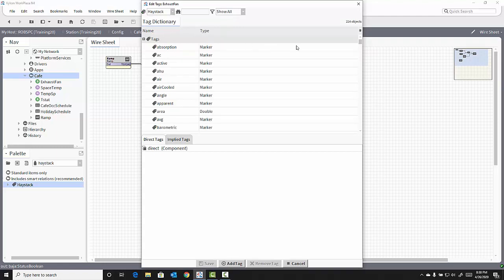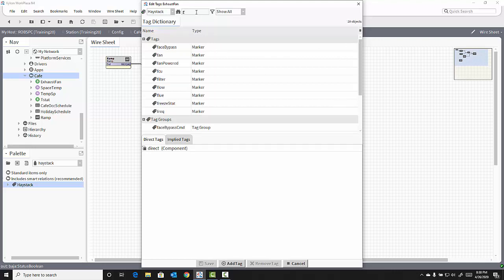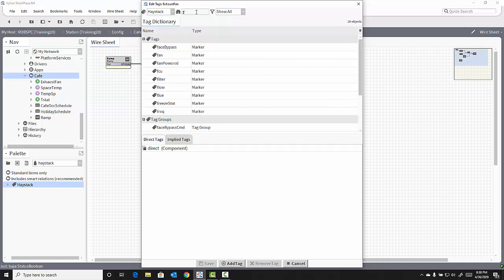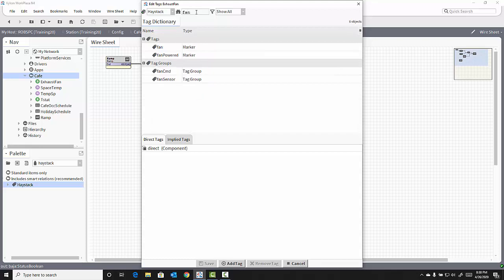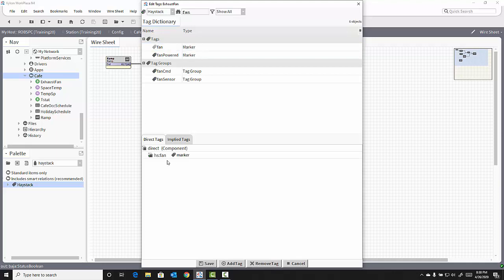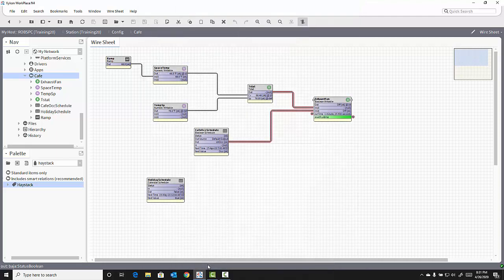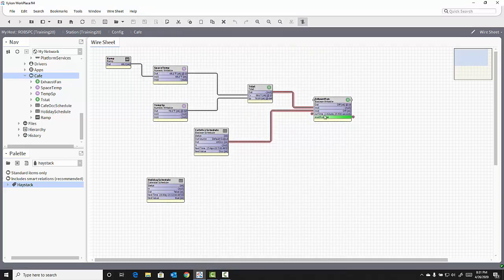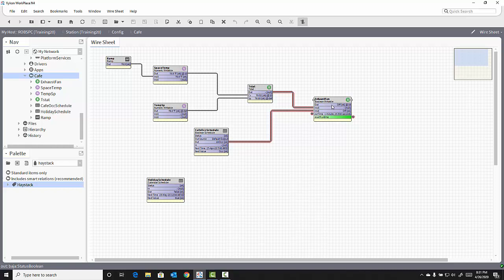Now, I could scroll through all the different tags that are available from that dictionary, or I could type in or filter the tag that I'm looking for, in this case, fan. To add the tag to the object, I can double-click on that tag, and it adds it to my direct tags. If I hit Save, that piece of metadata, that tag is now a part of the exhaust fan object's configuration.